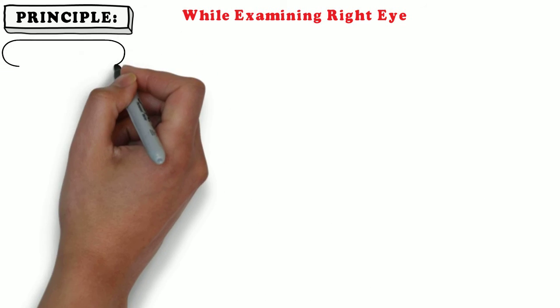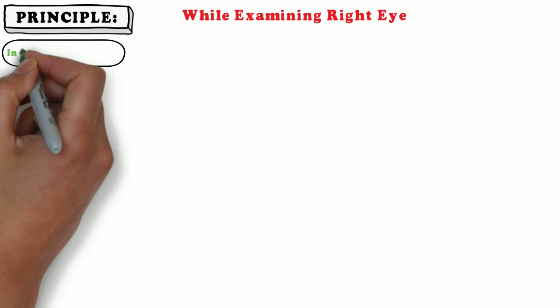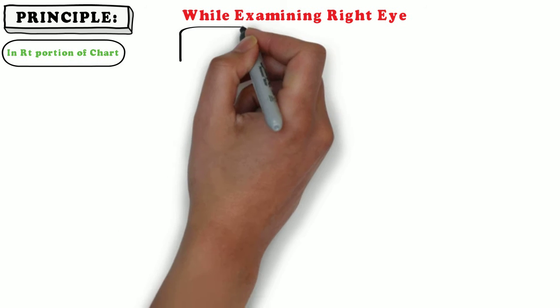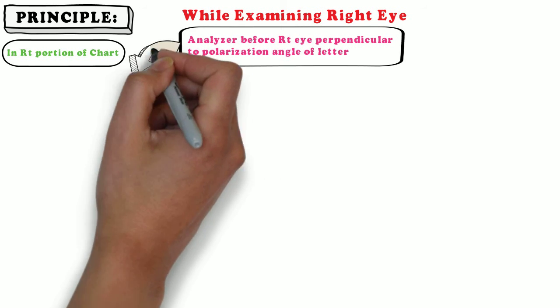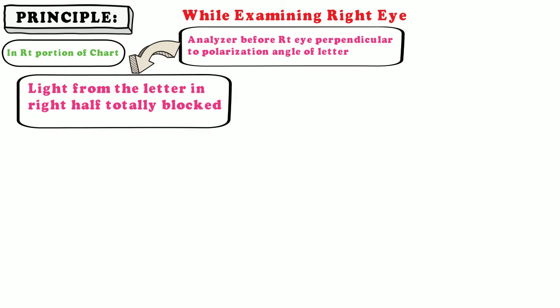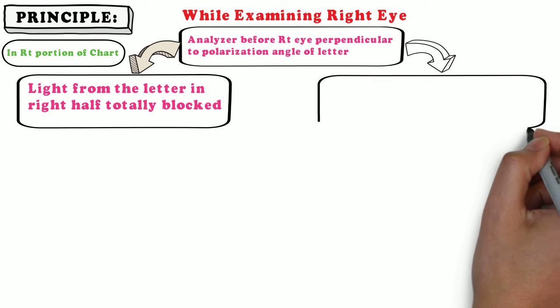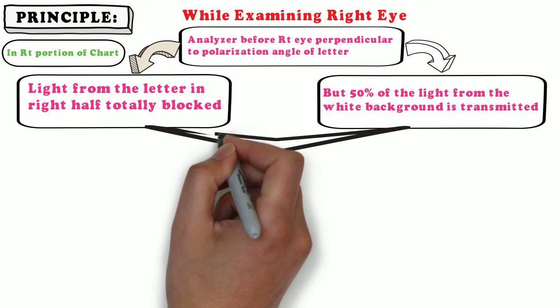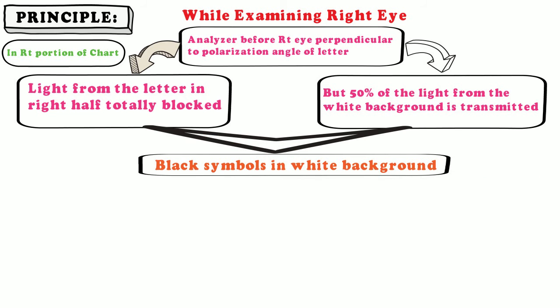Now let's study about the principle. While examining the right eye, let's see what happens in the right portion of the chart. The analyzer before the right eye is perpendicular to the polarization angle of the letter. Light from the letters in the right half is totally blocked, but 50 percent of light from the white background is transmitted. As a result, a black symbol in white background is produced.